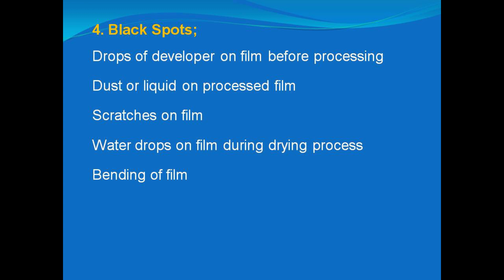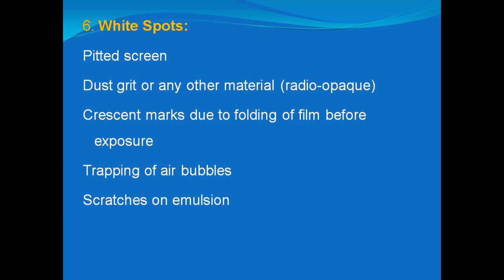Black spots arise when a drop of developer falls on the film before it is processed, or due to falling of dust or liquid on processed film, scratches on the film, water drops falling on the film during processing, or bending of the film when it is being processed.